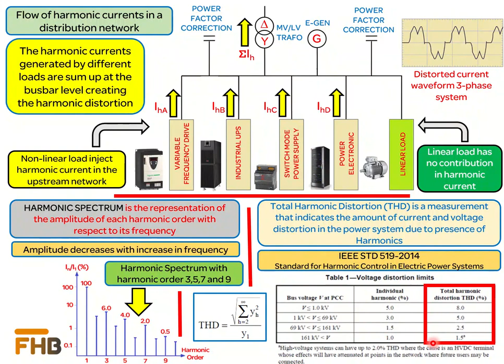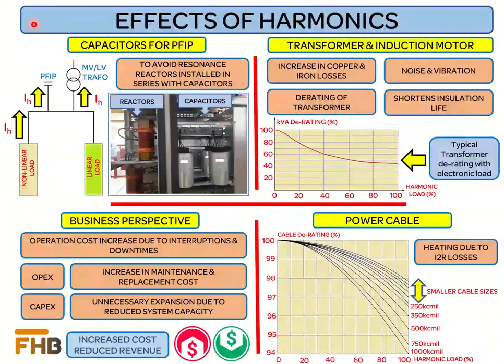Total harmonic distortion determines the level of harmonic distortion in the power system. The equation shown here produces a value at a point in the power system which indicates the distortion in the current or voltage. The harmonic order h can be limited to the 50th harmonic. However, for sensitive measurements it can go up to the level of the 100th harmonic. Utility companies are more focused on lower order harmonics such as the 5th, 7th, 11th and 13th. IEEE standard 519 represents the standard for harmonic contents in the power system. The total harmonic distortion limits for different voltage levels are shown here as reference.